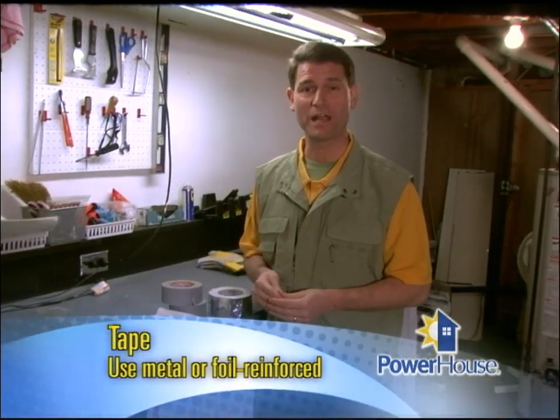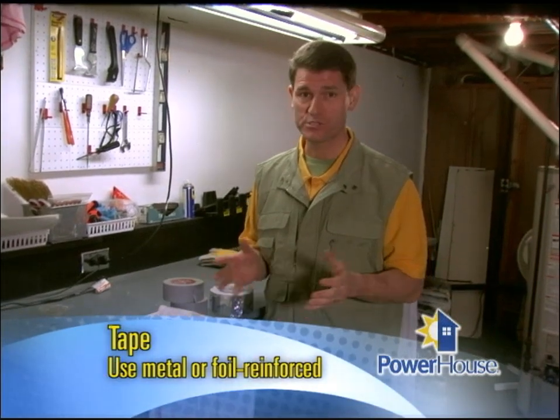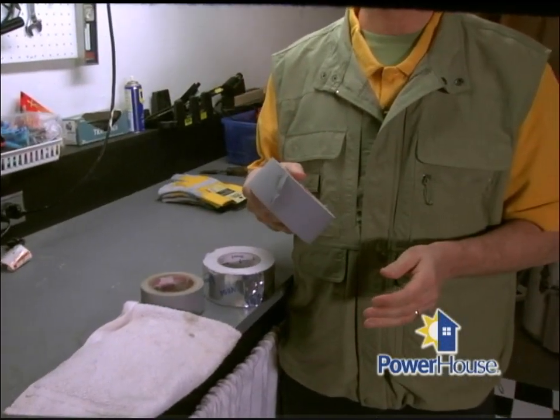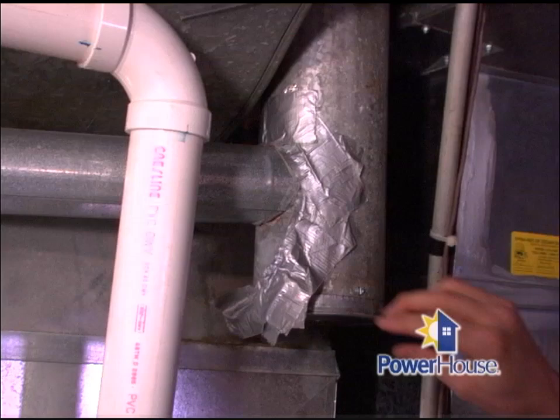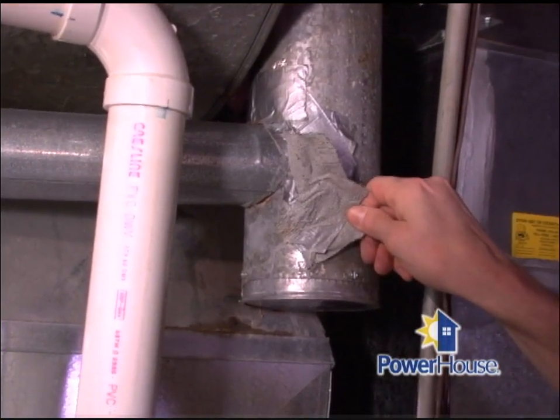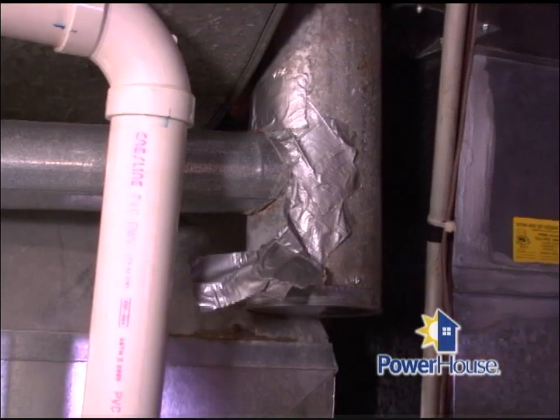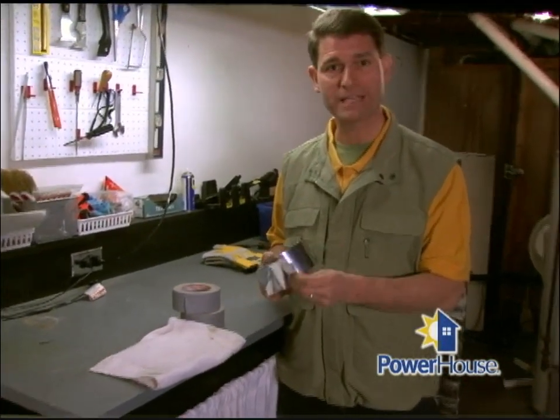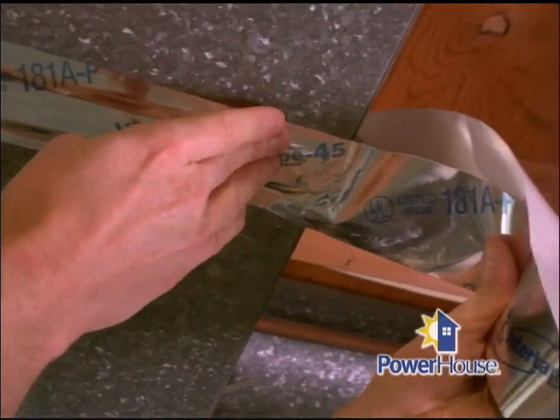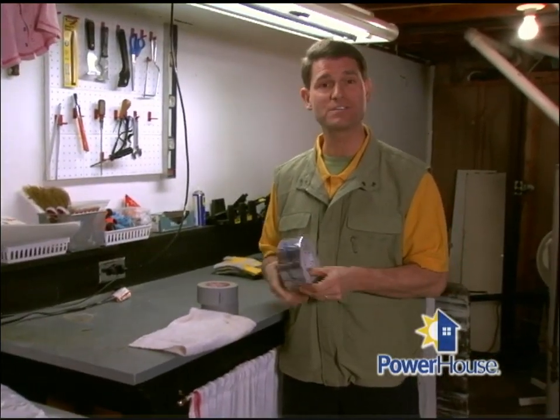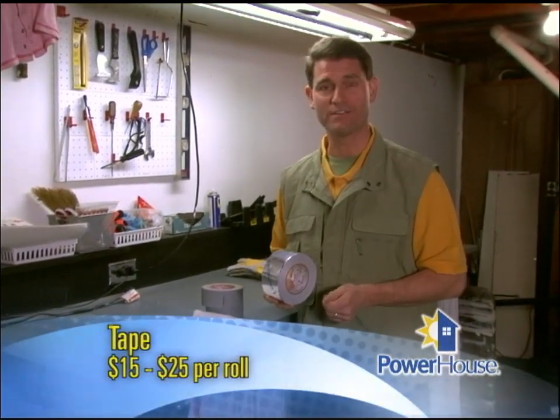A number of adhesive-backed tape products are available for sealing duct joints and seams. Generally, they're more convenient and less messy than mastic. Here's an important note about the silver gray cloth tape, commonly known as duct tape. It's great for many applications around the house, but it's not really good for sealing ducts. The heat from the duct hardens the adhesive, and over time it loses its stickiness, dries out, and cracks, and the duct leaks again. Instead, metal reinforced or foil-backed tapes are the preferred choice. It's designed specifically to withstand a duct system's heating and cooling cycles and will not deteriorate. Foil-backed adhesive tapes are generally available in 100 and 150-foot rolls, and they cost from about $15 to $25 per roll.